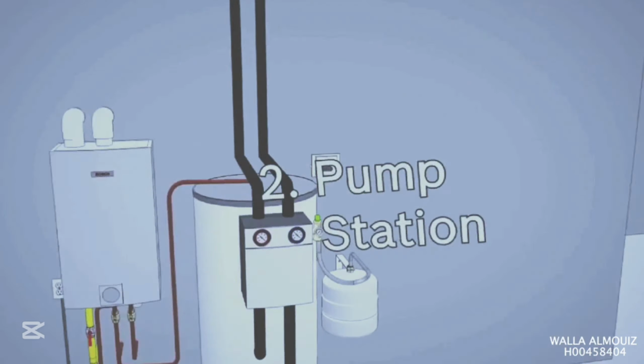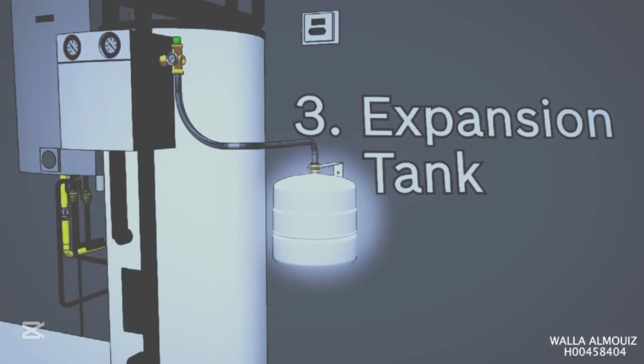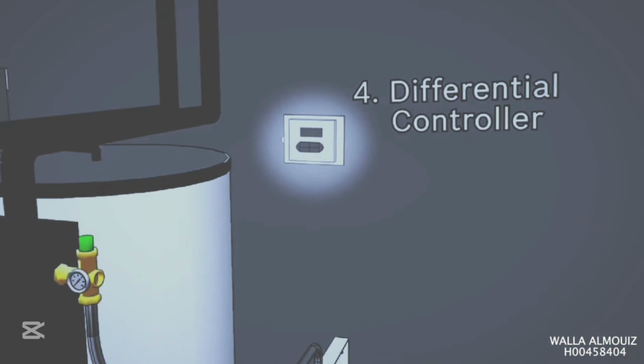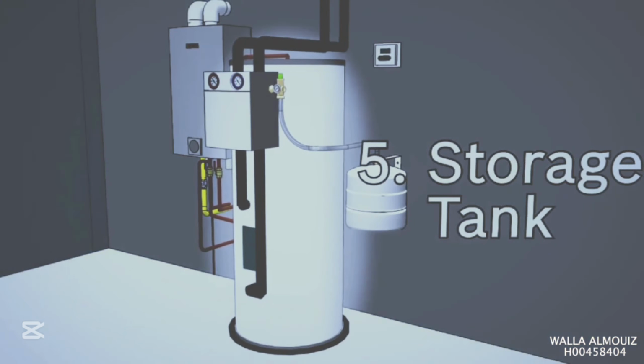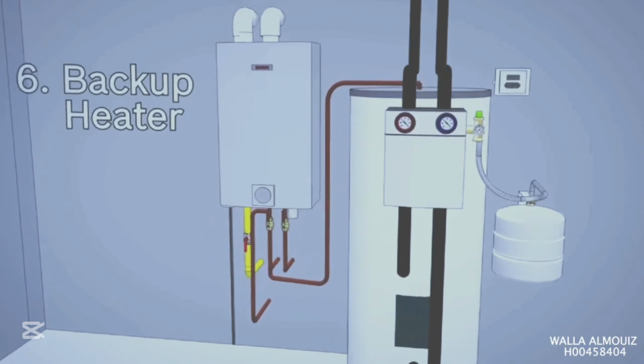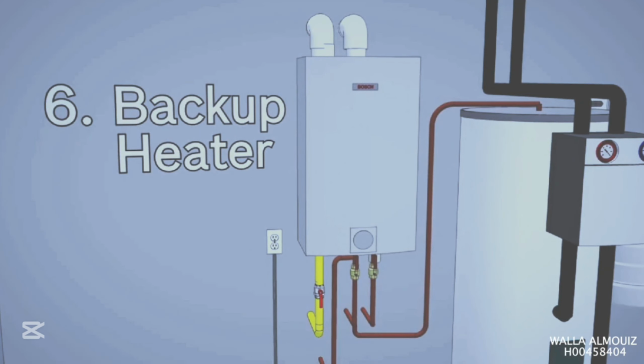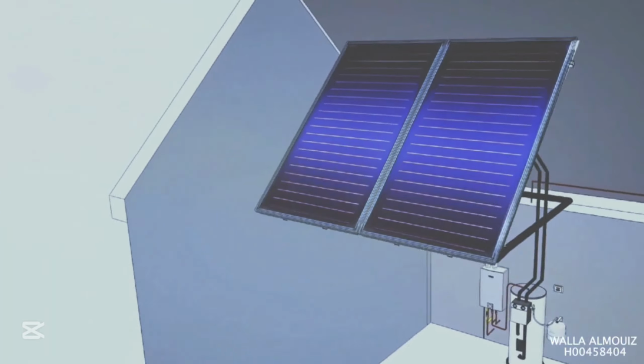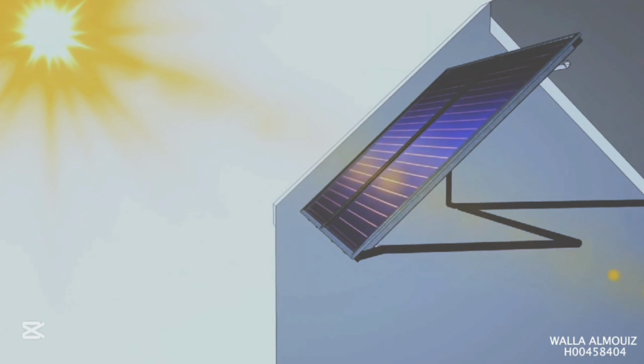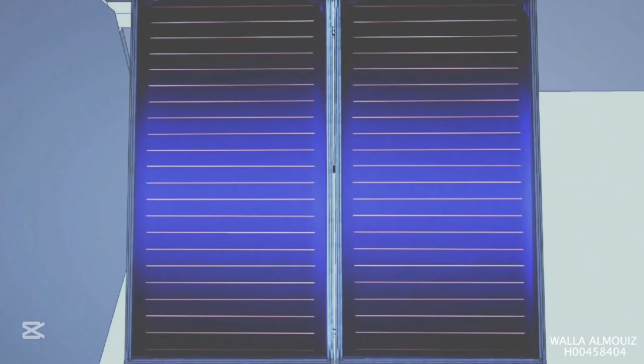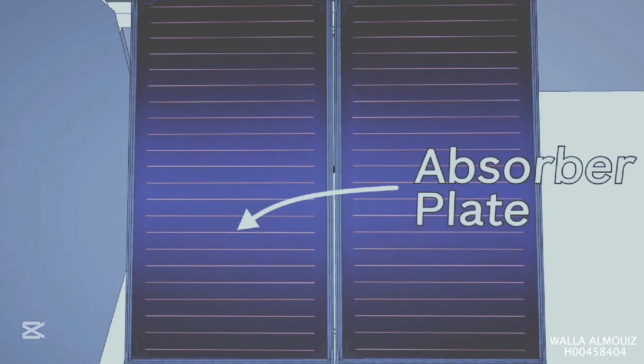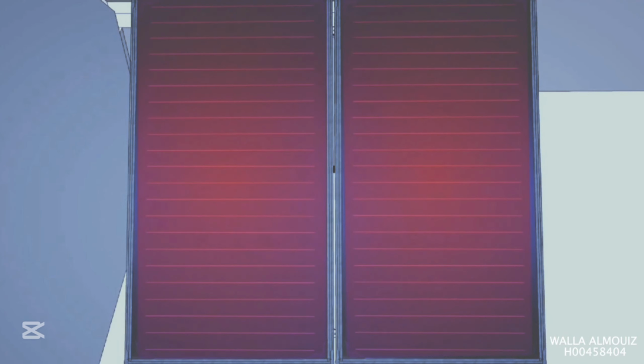The solar hot water system includes solar collectors, a pump station, expansion tank, differential controller, hot water storage tank, and backup heaters such as a boiler or tankless water heater. Energy from the sun transfers through the glass of the collector and is absorbed by a component called an absorber plate. The absorber plate has a special coating designed to capture as much solar energy as possible and convert this energy into heat.